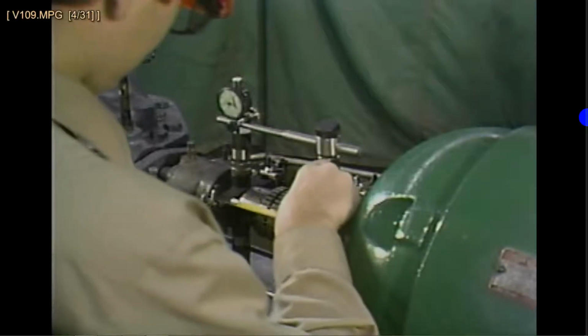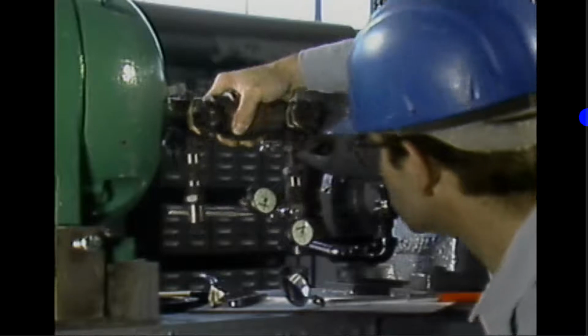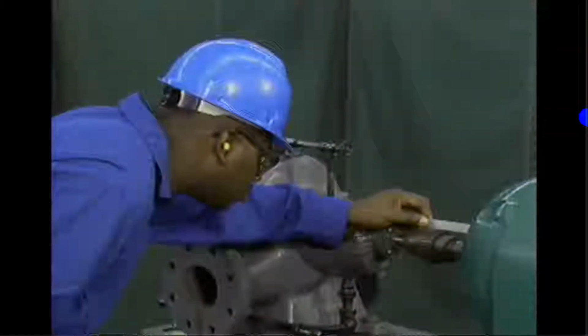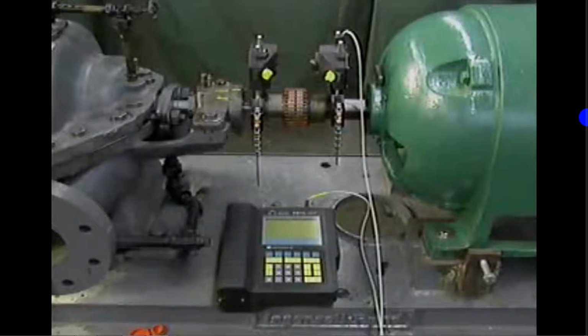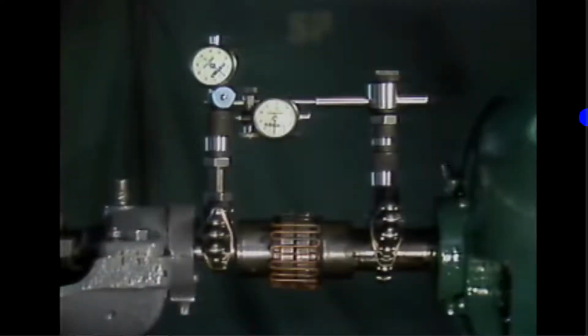Correcting misalignment requires a number of measurements. And the way those measurements are made depends on the type of alignment procedure being used. Some alignment techniques use only a straight edge and a feeler gauge. Others rely on complex instruments such as laser alignment equipment. But often, measurements are made with dial indicators. Two types of dial indicators are generally used for alignment work: the balanced type and the continuous type.